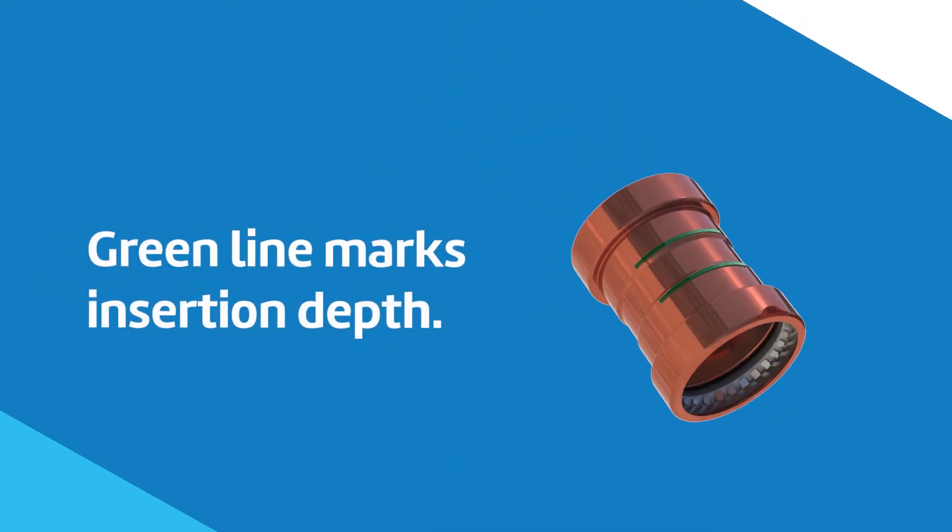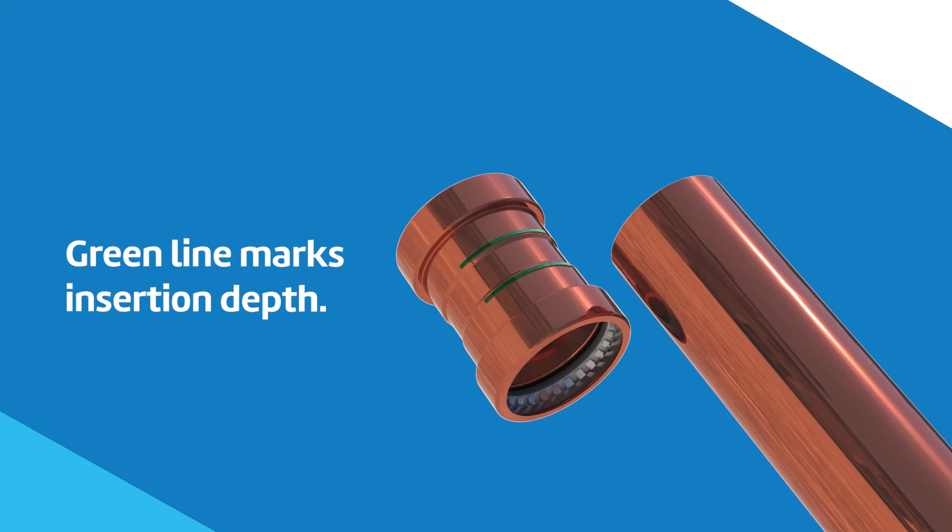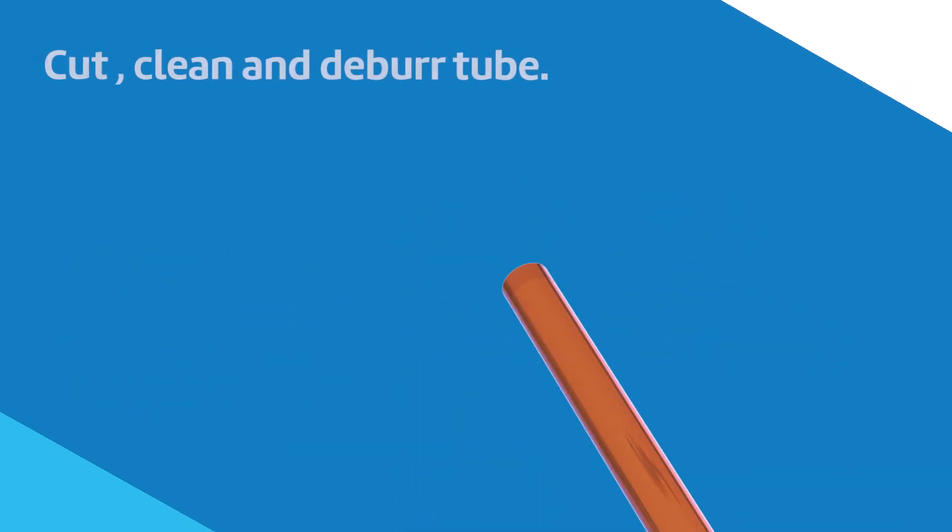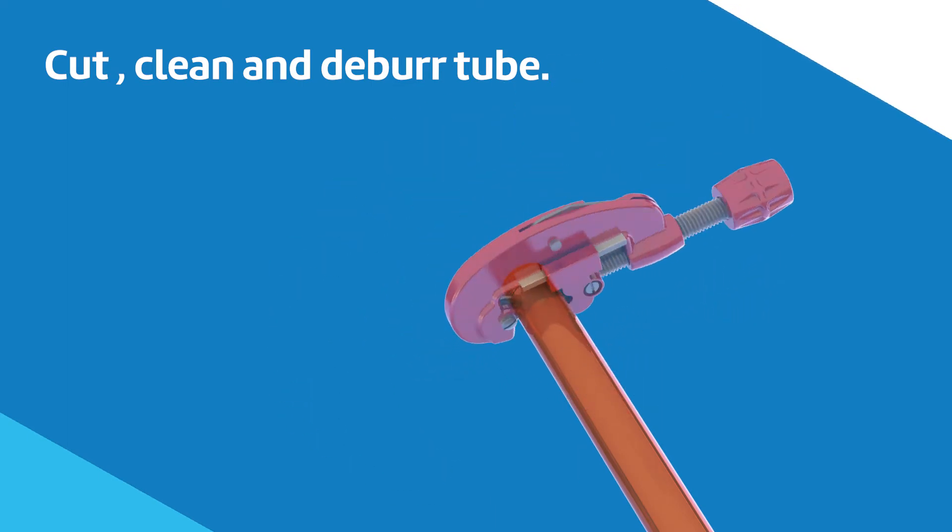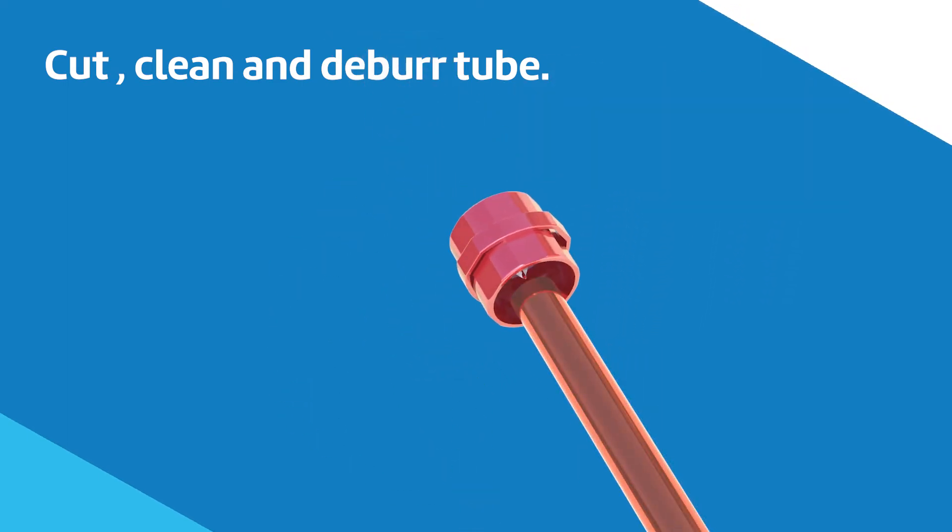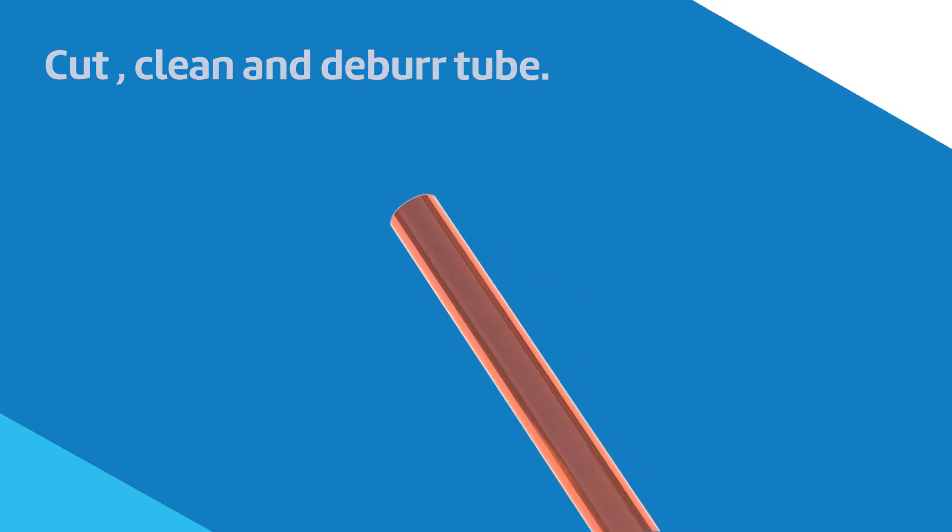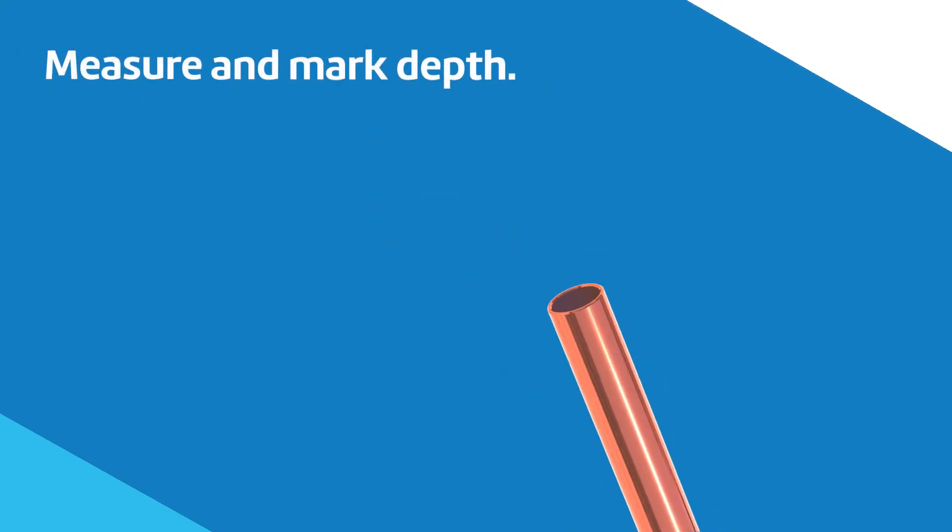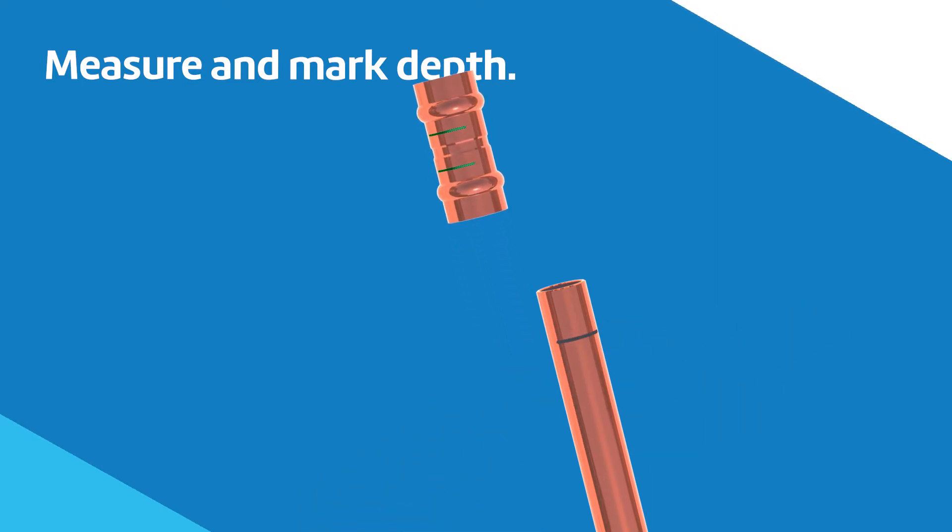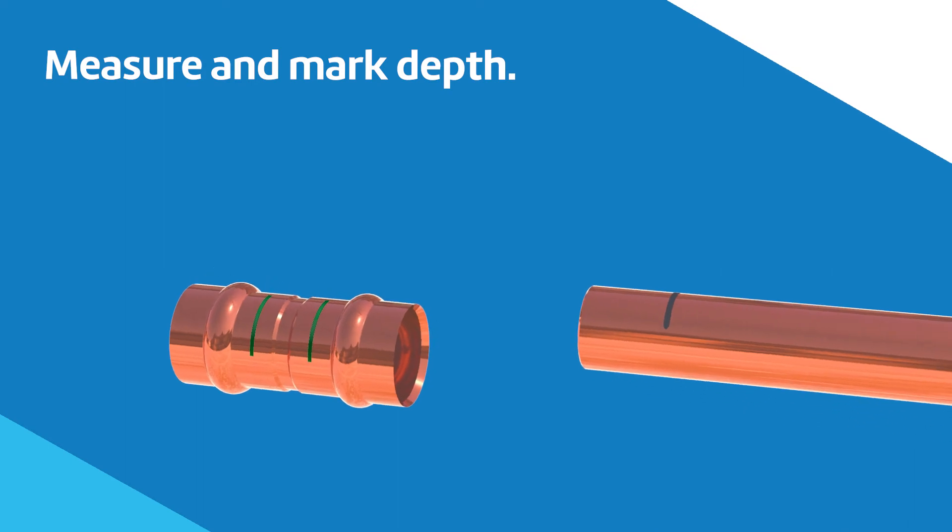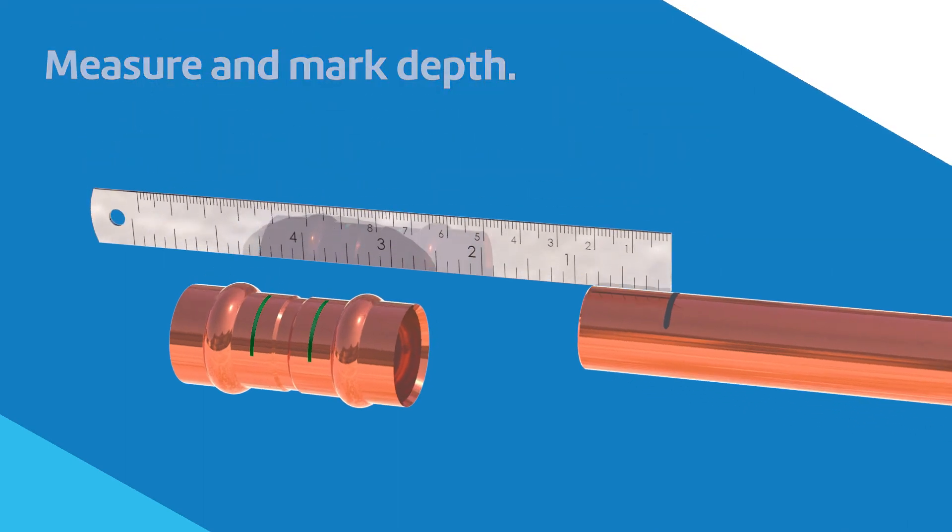The green line on SCI Copper Press product exteriors marks the proper pipe insertion depth. Follow these simple steps for proper installation of SCI Press products. After cutting, cleaning, and deburring the tube, it is recommended to measure and mark the depth the press fitting is inserted to on the pipe to ensure that it is installed according to the recommended depth and that the fitting has not moved over time.